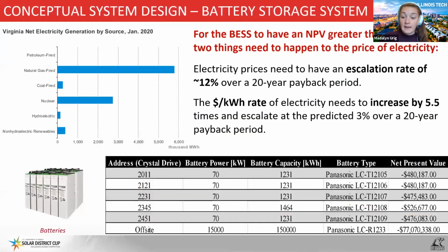Once we ran the REACT simulation for all of the arrays, the finances of the project were not advantageous. As you can see in the table, the net present values are negative by hundreds of thousands of dollars. Even running financially optimized simulations, REACT suggested not even including a battery energy storage system. This is because the market for electricity is very cheap in Arlington. It is difficult to implement new infrastructure and have it compete with existing cheaper options.